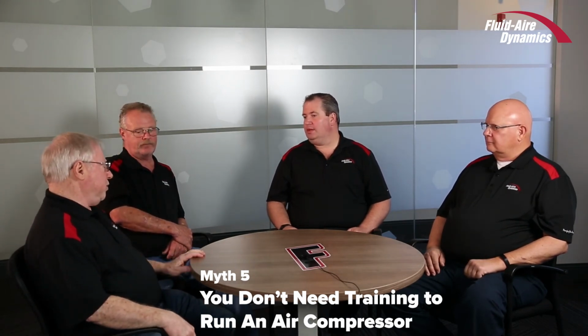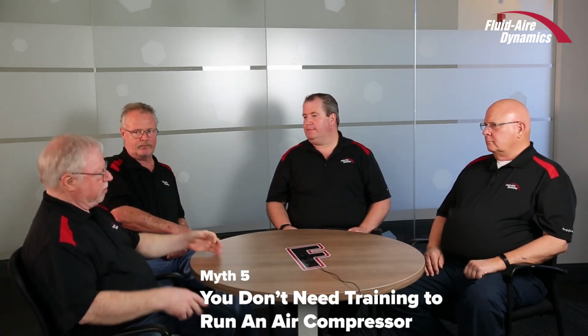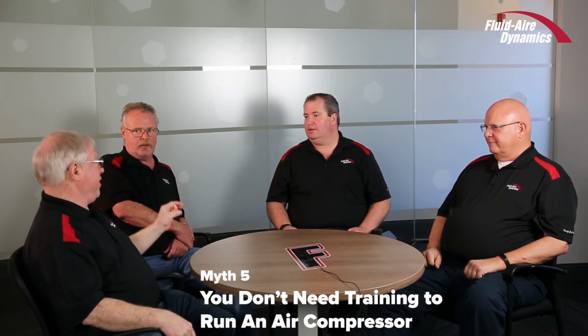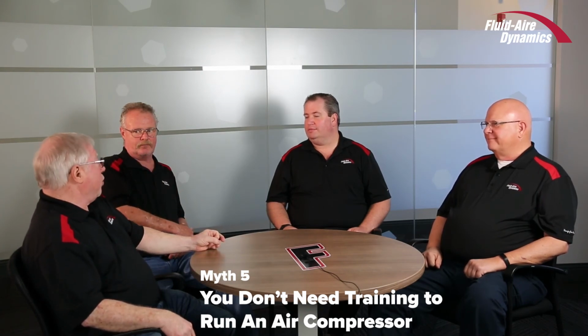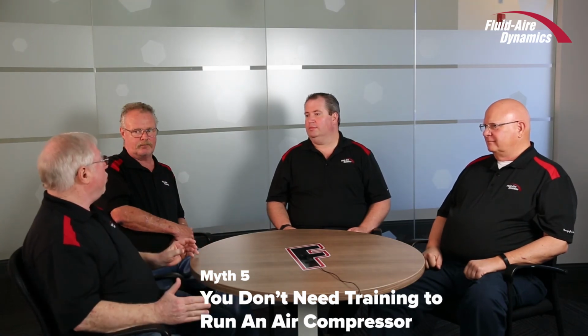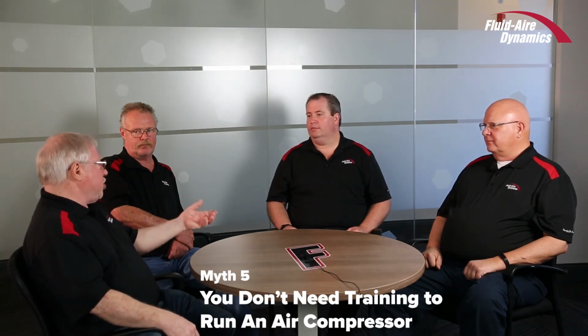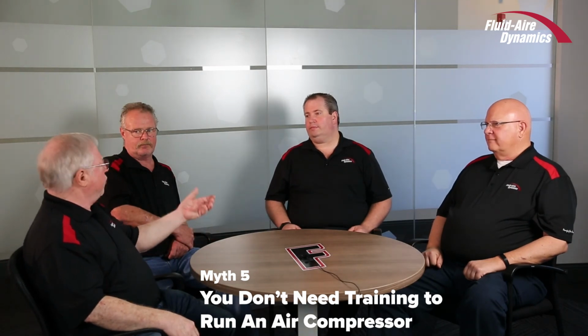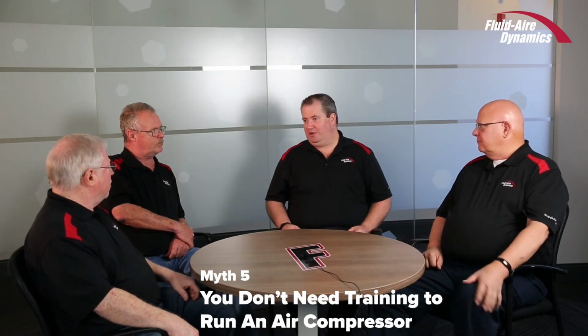Talking about couplers, most companies have 3/8-inch couplers or 1/4-inch couplers, so they use them all over the plant, no matter what it is. But there are 1/2-inch couplers out there, and they're using a smaller 1/4-inch coupler when it should be a 1/2-inch. And the issue becomes, you have to know that there is a difference. That pressure drop across that is enormous. Just a standard coupler flowing 20 cubic feet is going to have a 3 or 4 pound drop. So you can't manage it if you don't measure it. That's right.